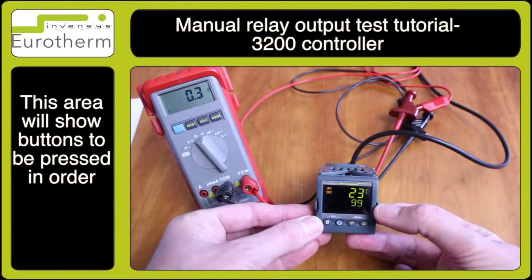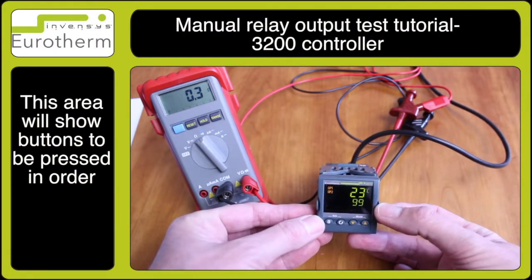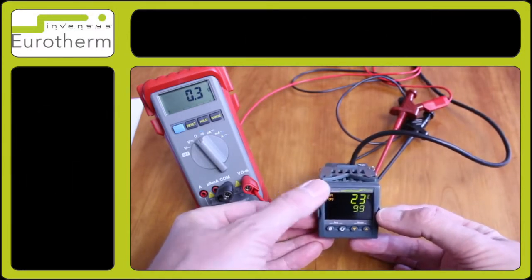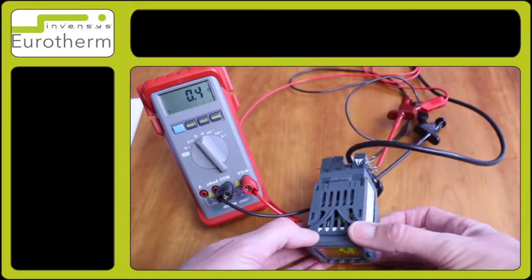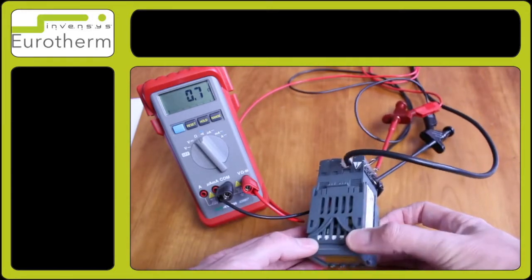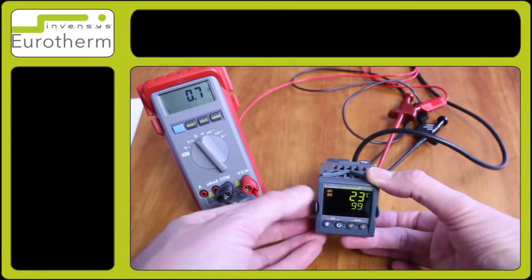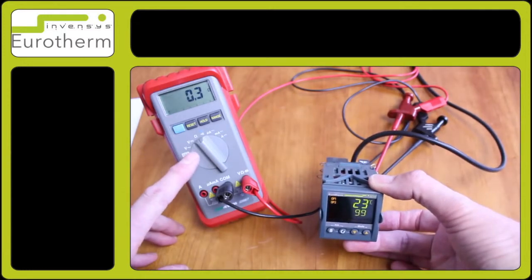In this tutorial I will demonstrate how to test your relay output is working. I would suggest switching off the controller and removing the relay wires and screwing down the terminals on the back of your instrument. In this particular test I've connected up a digital multimeter with an ohmic setting and connected it to our relay output.